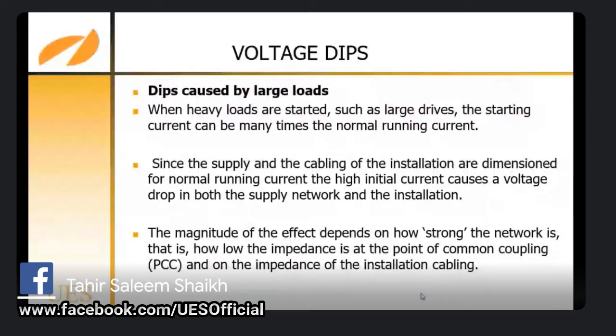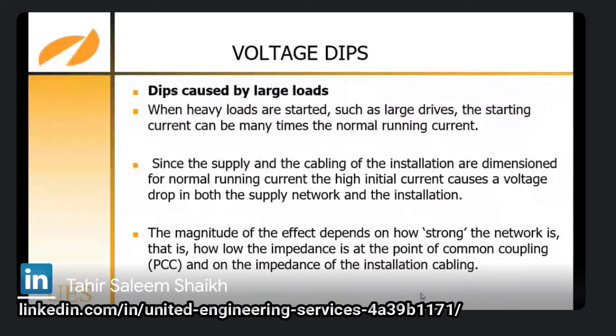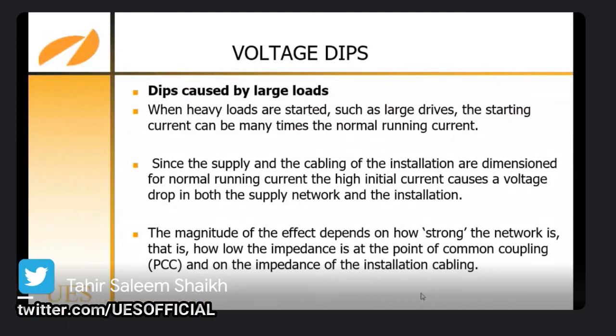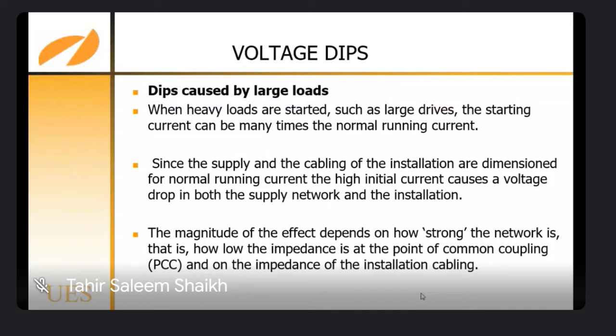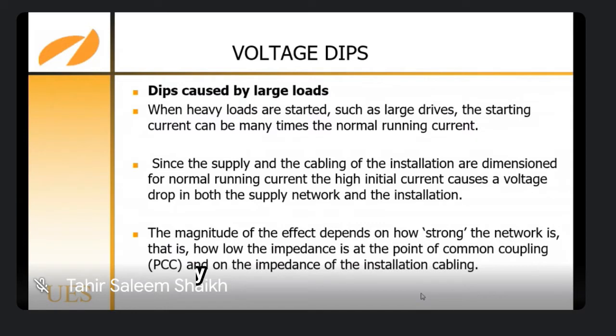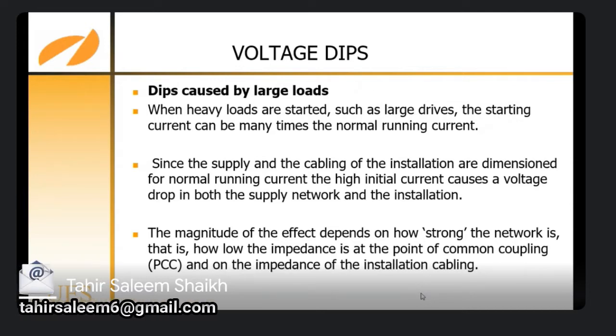And you have to decide, according to your process plant, how much dip is allowed. Normally a 25 to 30% dip may be allowed, but generally for sensitive loads it should not be more than 5%. The magnitude of the effect depends on how strong the network is, that is, how low the impedance is at the point of common coupling, and on the impedance of the installation cabling.